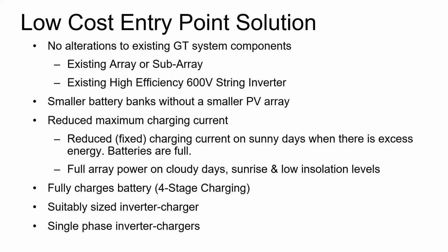So in terms of selling power, every bit is important with regards to the reimbursement structure or net metering. You want to preserve as much of that power going back to the grid as possible, and having the higher efficiency operation of the string inverter is important there. You can also accommodate smaller battery banks without having to size them in tandem with your PV array. That's really nice, since the two can be independently sized. It's not a domino effect where changing one thing affects the size of every other component.